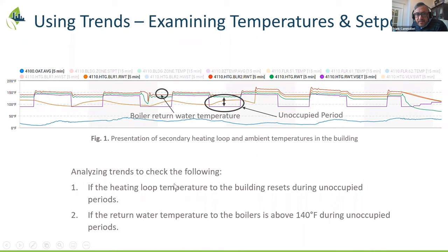If you're looking at the heating loop temperature, we want to make sure it resets during unoccupied periods. The whole point is that during unoccupied periods, we want the building to use less energy, so there's no need to heat it as much - reduce the unoccupied temperature setback. We're looking to see if it's actually doing that.